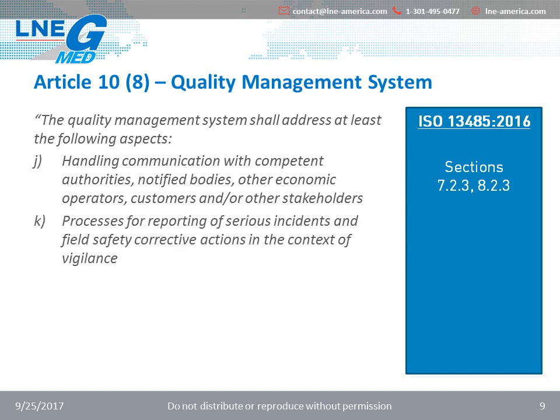The process for reporting serious incidents and field safety corrective actions in the context of vigilance is also covered by section 8.2.3, but also by section 8.2.2, which is related to the documented procedures of complaint handling. So again, here we see the correlation. The communication, which is 8.2.3, and in this case of a serious incident, you see we have a communication, maybe to a competent authority, to the notified body, to different elements depending on the incident. But we also have these procedures of collecting this information, and this is in the complaint handling in section 8.2.2.